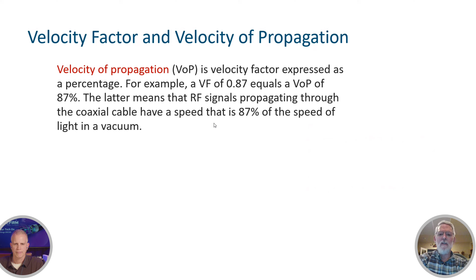Oh yeah, more math, easy though, I promise. If the cable's got a velocity propagation of 87%, that's hardline cable in most cases, and the RF is traveling through that cable. Here's how you figure out the speed: speed of light in feet per second is 983 million and change, times 0.87, so the RF is going through the coax at 855 million and change feet per second.